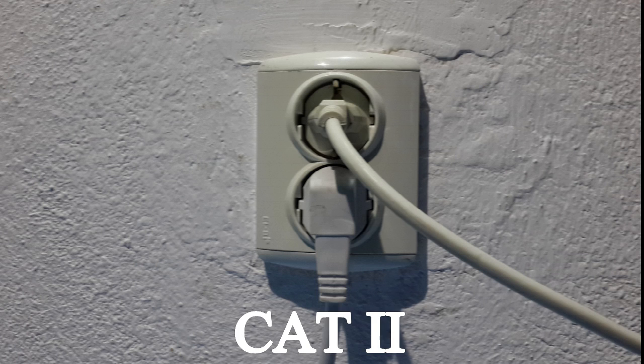CAT 2 means all equipment that we connect to the AC outlet. Anything related to 100 volts, 120, 220, or 240 volts AC is CAT 2 equipment. We should not use CAT 1 equipment on it, because we expose the equipment to damage from high voltage or high current, or we expose ourselves to injury. That means I can use CAT 1 equipment to test electronic boards, but if that equipment has outputs related to AC voltage, I must use CAT 2 equipment on those outputs.